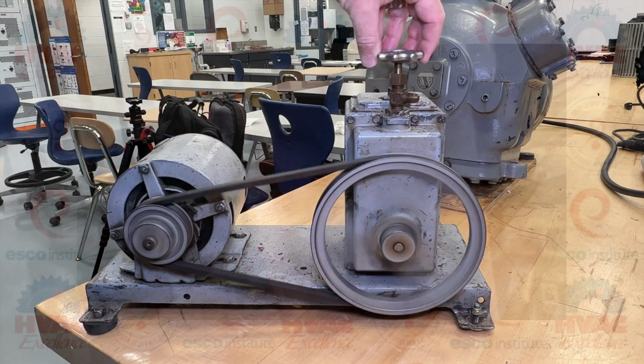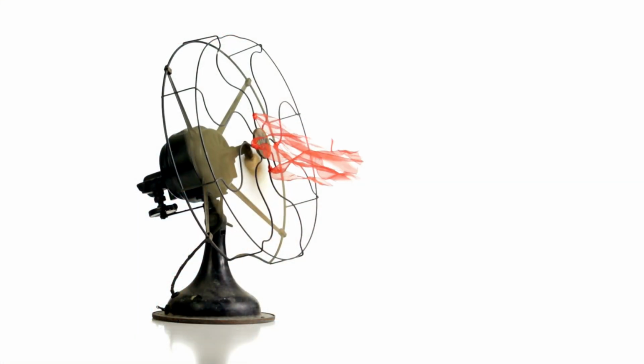Beer can cold, that's what the suction line should feel like. Run the vacuum pump until you don't get a puff of air out when you remove your finger from the discharge. Stop the evaporator fan and wait until frost comes out of the suction line. Look at the streamers on the register. If they are flowing straight out, you have enough air. All these technologies were taught at one time.